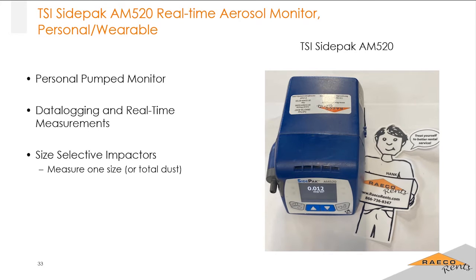If the levels do go high, you can set alarms on these, which is something that I failed to mention. Everything I've gone over today, the gas monitors, the DustTraks, the SidePaks, you can set alarms on these. If an alarm goes off, the screen will start flashing red. You might hear an audible noise. It depends on the settings, but you can adjust those alarm settings, for example vibration and a flashing light, or an audible noise. There are different combinations, but just know that you can set alarms on these and it will alert you accordingly.